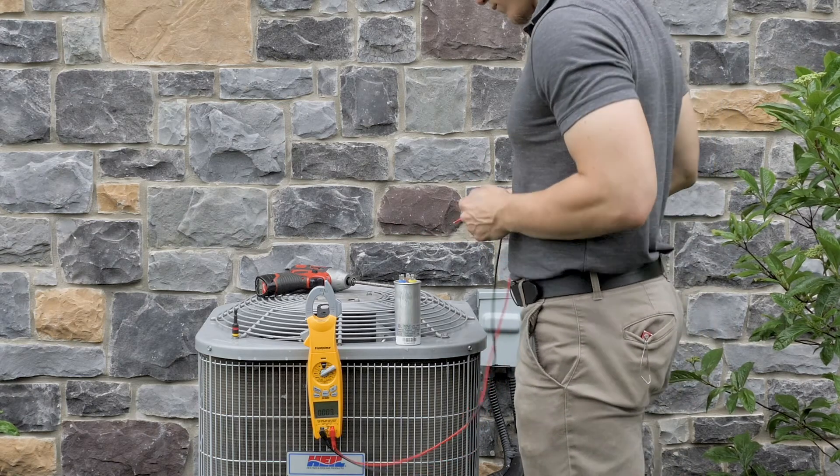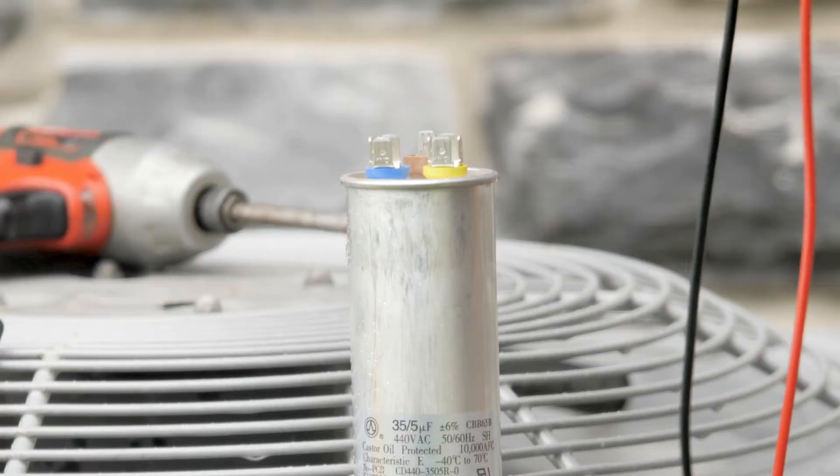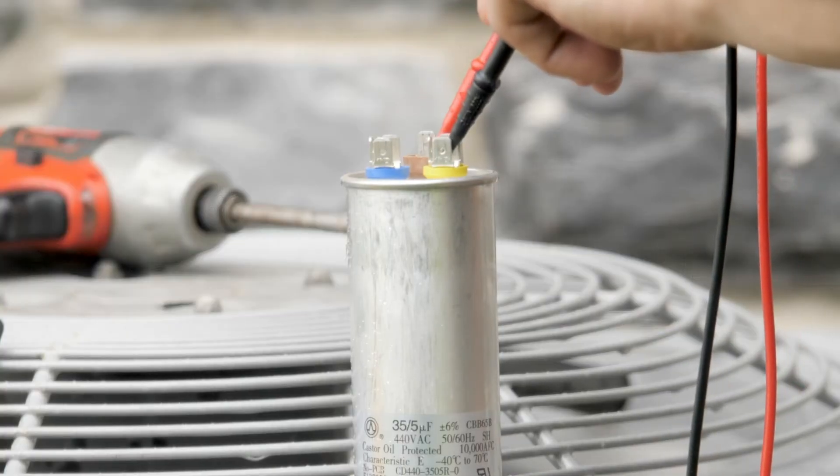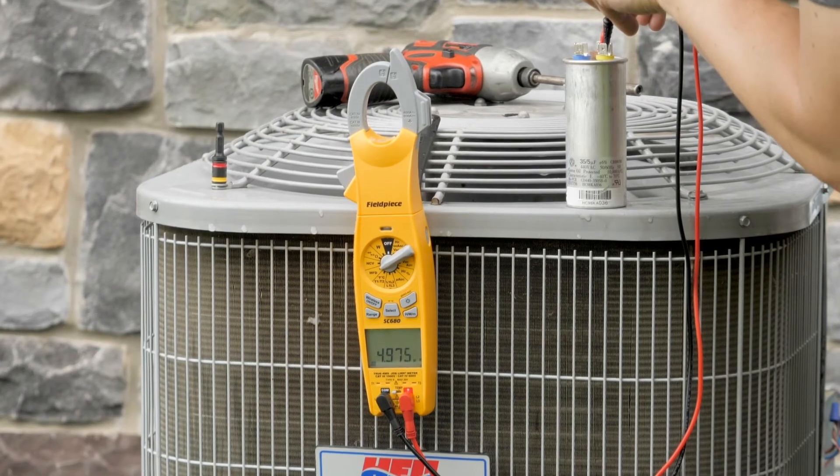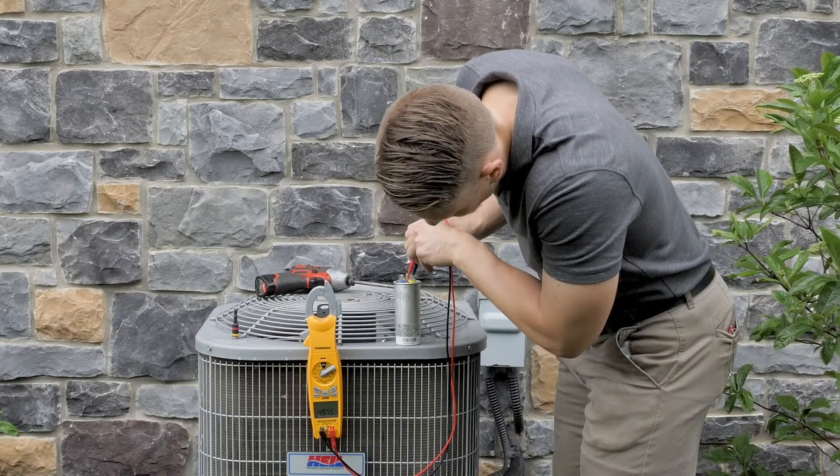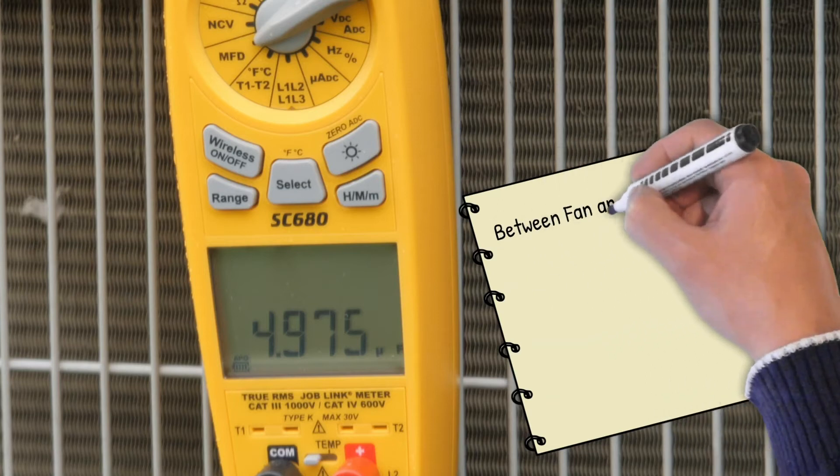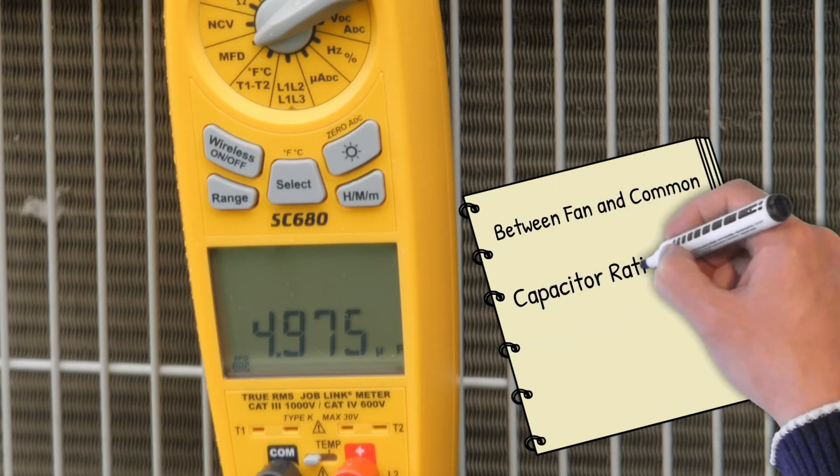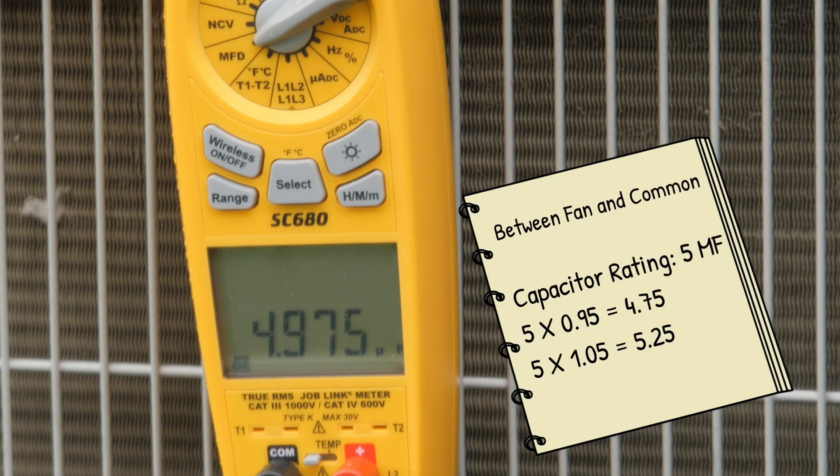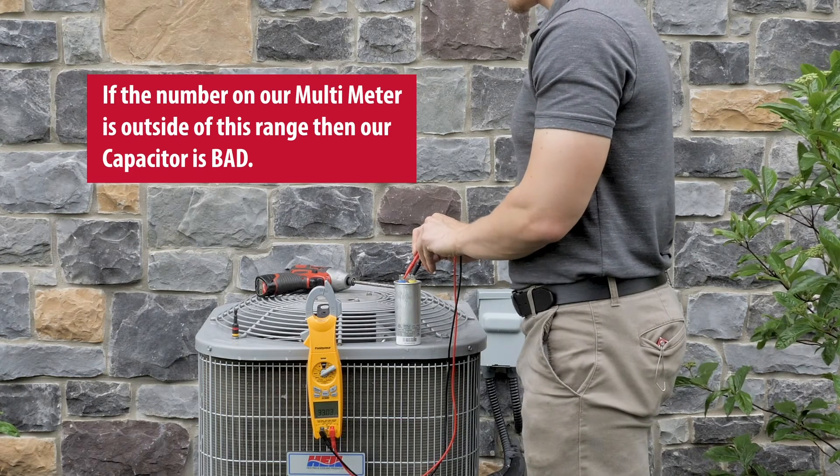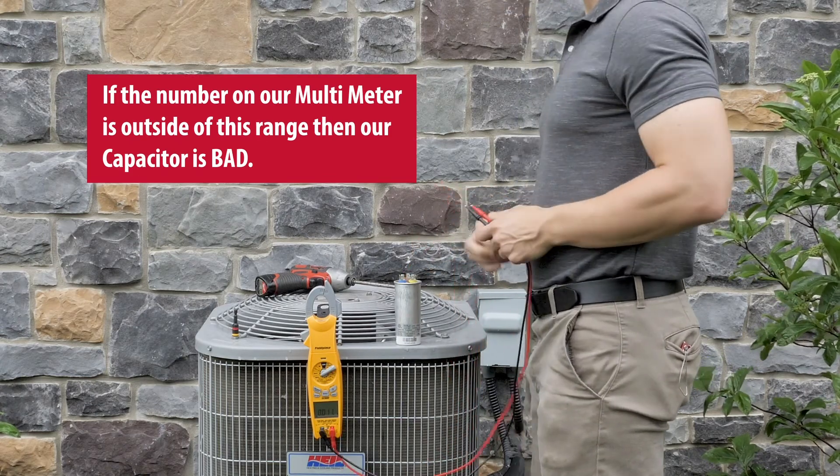Now it's time to check the capacitor. We'll start by measuring between the fan and common terminals. We're looking for a number between 4.75 and 5.25. We get this range by multiplying our capacitor rating of 5 microfarad by 0.95 and 1.05. If the number on our multimeter is outside of this range, then our capacitor is bad.